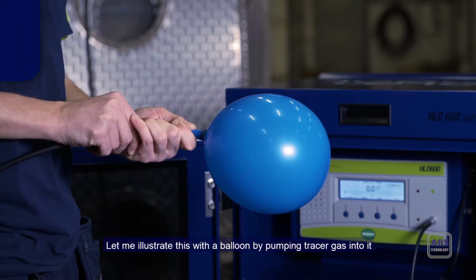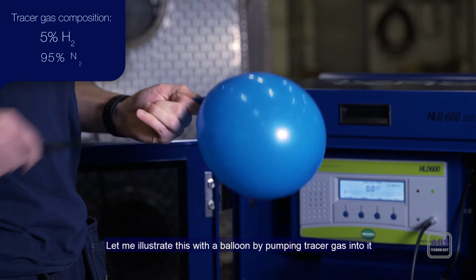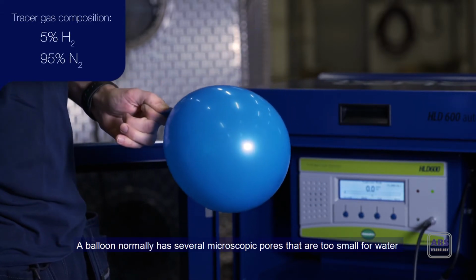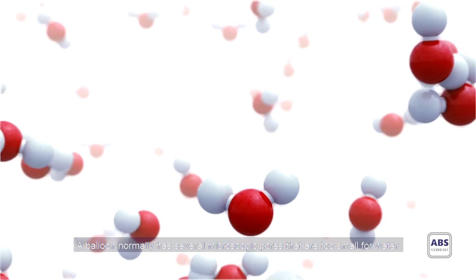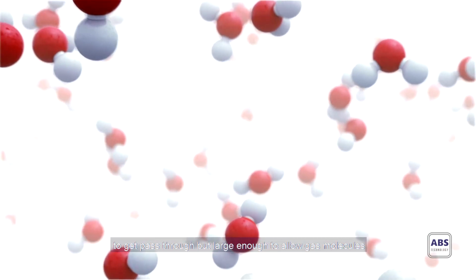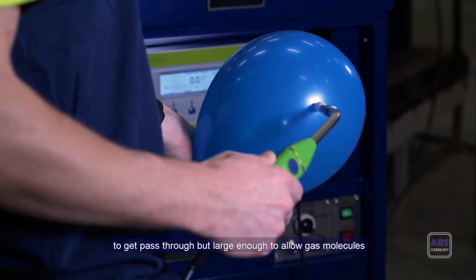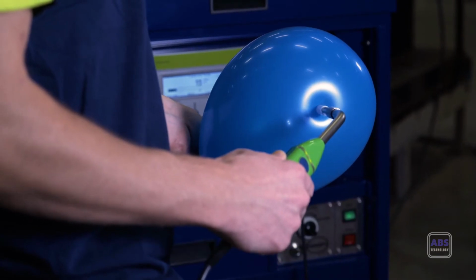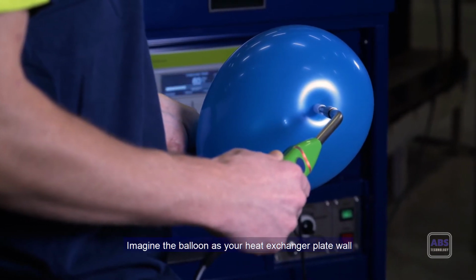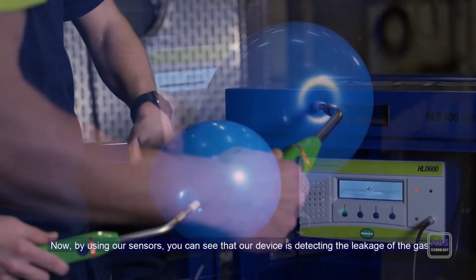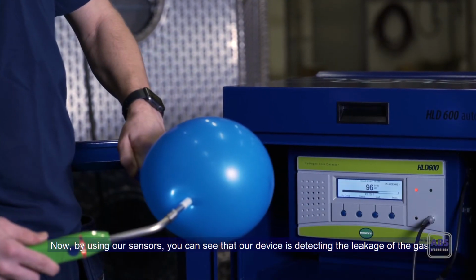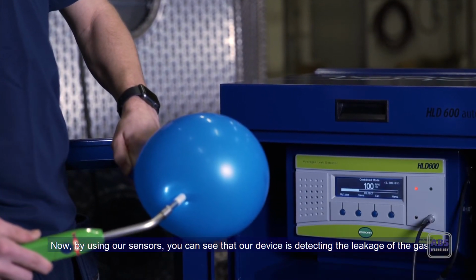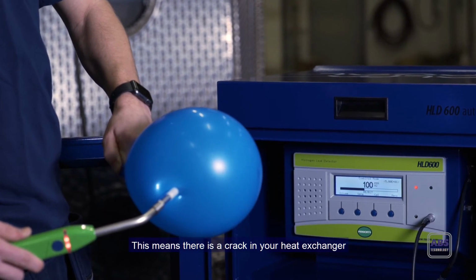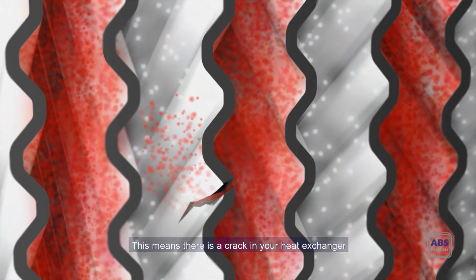Let me illustrate this with a balloon by pumping tracer gas into it. A balloon normally has several microscopic pores that are too small for water to get past, but large enough to allow gas molecules through. Imagine the balloon as your heat exchanger plate wall. Now, using our sensors, you can see that our device is detecting the leakage of the gas. This means there is a crack in your heat exchanger.